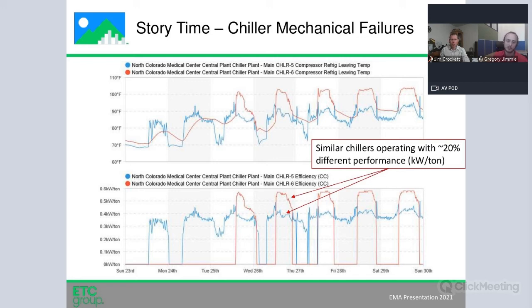We had been looking at these chillers, their sister or twin chillers here, and you can see in this top graph is the refrigerant leaving temperature. And this red line is chiller 6, and the blue line is chiller 5. And the same thing applies down here. This is their efficiency over the same time. So, the red line here showing the significantly warmer refrigerant leaving the compressor.